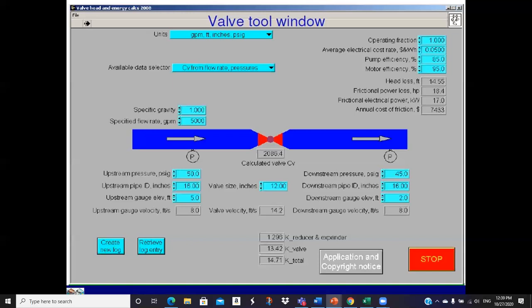Okay. Up in the upper right-hand corner, it's going to do a cost calculation. So it's the same operating fraction: what portion of the year is the valve in this position? What's our cost of electricity? And what are your estimated pump and motor efficiencies? In this case, we're at 85 and 95. So it calculates the head loss in feet across this valve, the frictional power loss in horsepower, and that's flow times feet of head times specific gravity divided by 3960. Simple calculation. What's the frictional electrical power when you take into consideration the efficiency of the pump and the motor? So how much pump energy are we really eating up with this valve in this position?